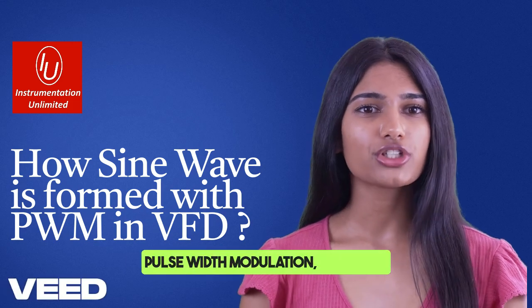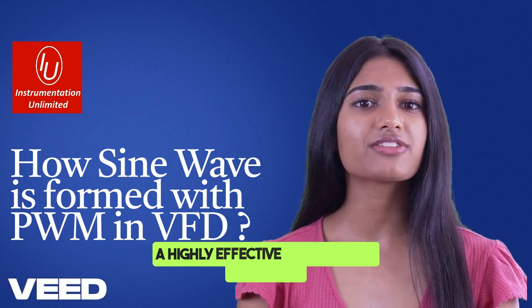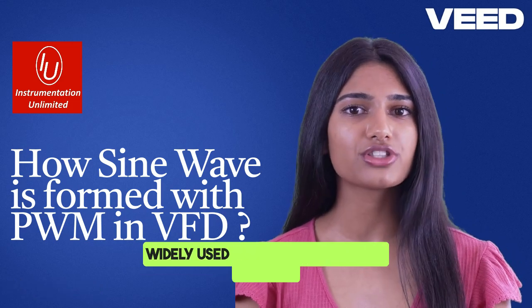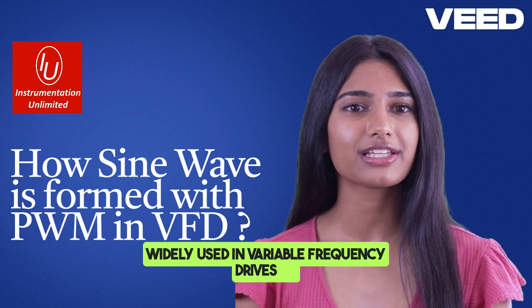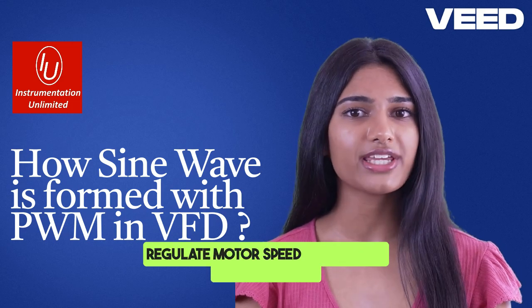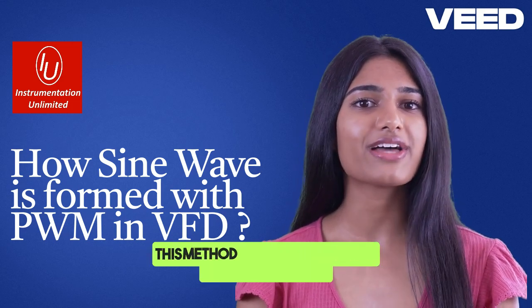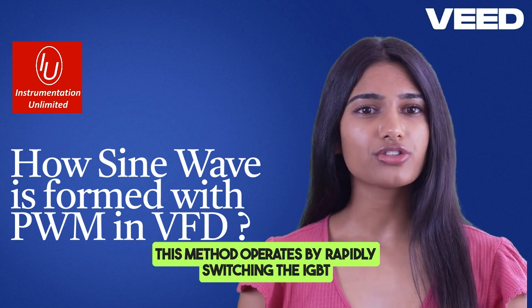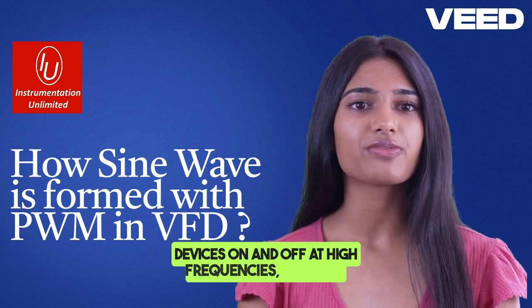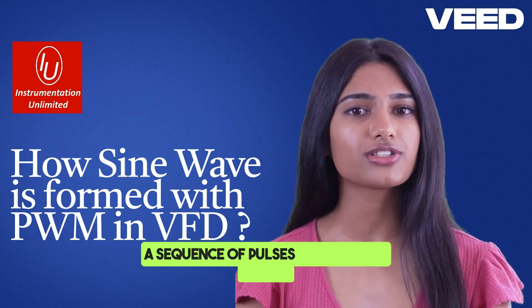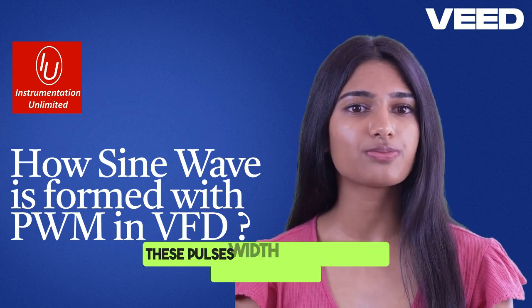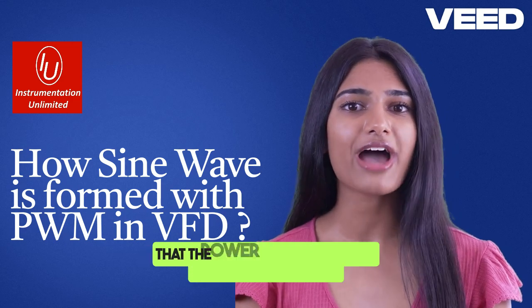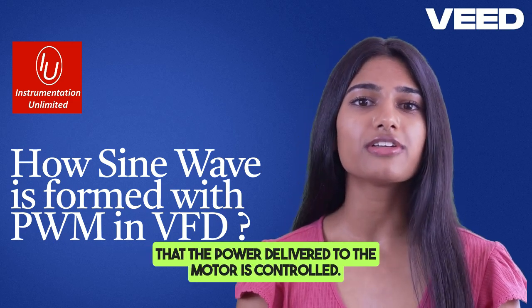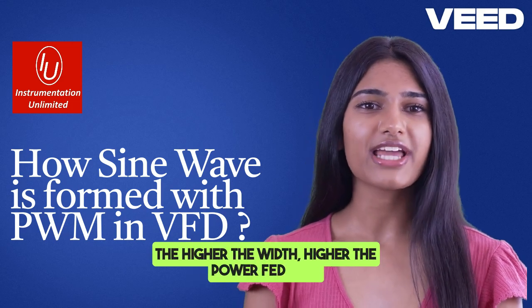Pulse Width Modulation, or PWM, is a highly effective and versatile technique widely used in variable frequency drives, VFDs, to regulate motor speed and torque with precision. This method operates by rapidly switching the IGBT devices on and off at high frequencies, creating a sequence of pulses with varying widths. The pulse widths are adjusted in such a manner that the power delivered to the motor is controlled. The higher the width, the higher the power fed in.